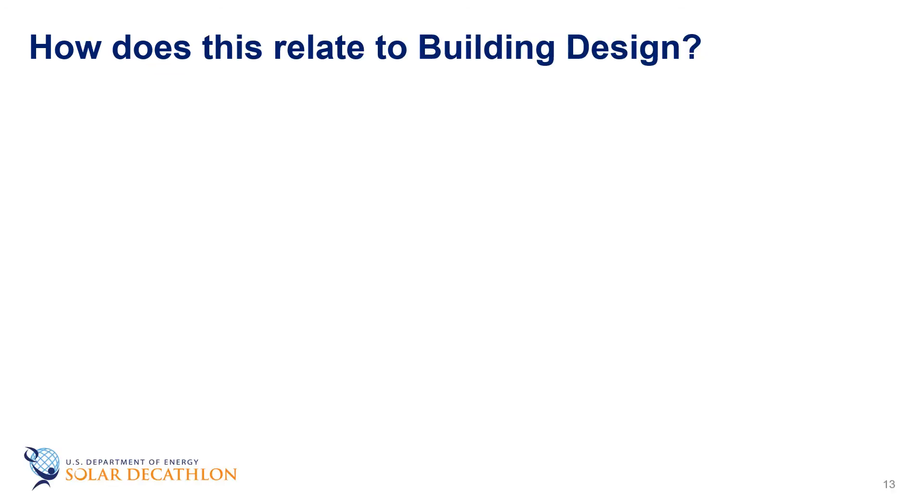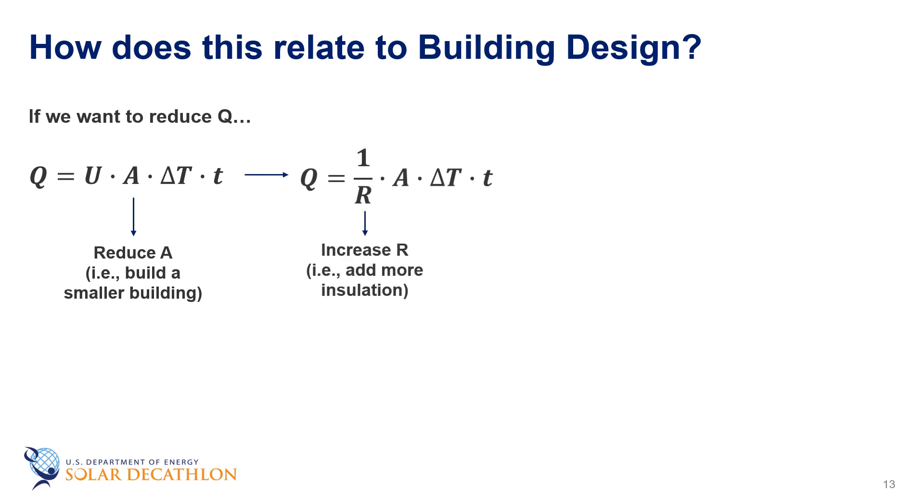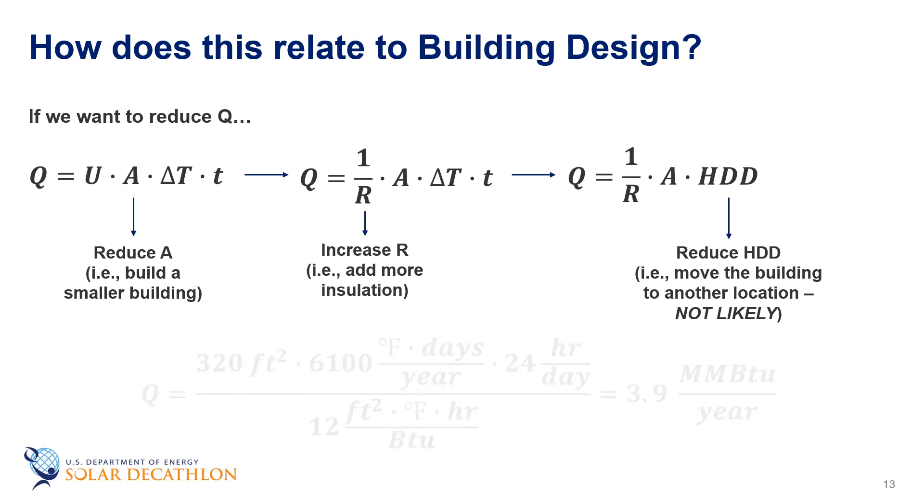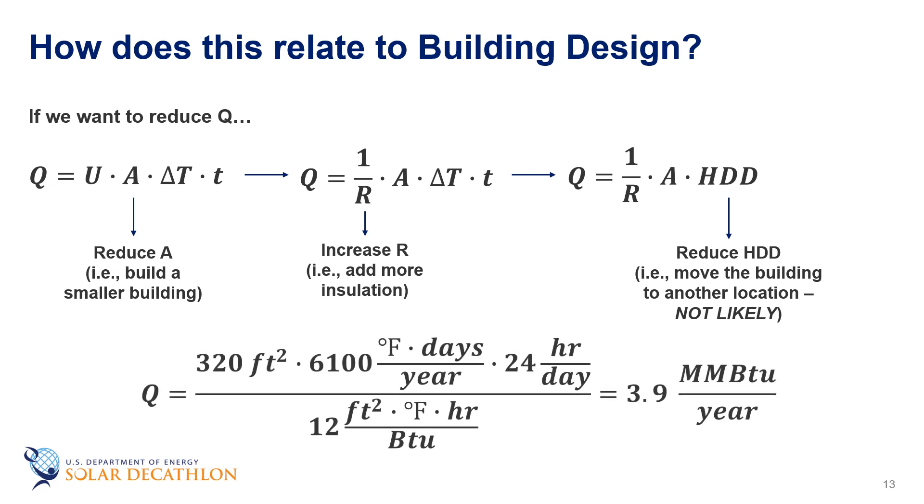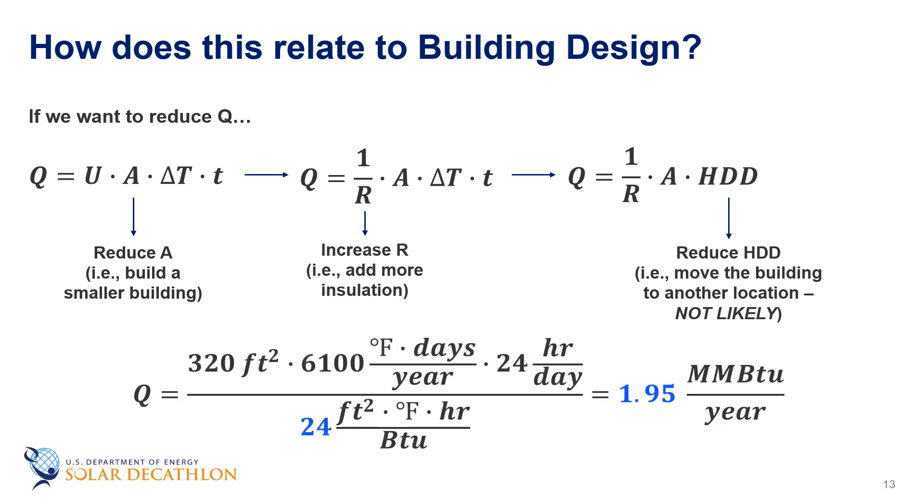Starting to think about design, we can reduce this number by having a smaller wall, i.e. a smaller building, increasing the value of R, or reducing the number of heating degree days by moving the building to another location, which is probably not likely. Often the solution is to choose to increase the insulation. So, for example, doubling the insulation from R12 to R24 will reduce the heat transfer in half to 1.95 million BTUs per year.